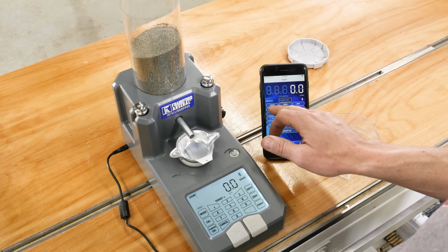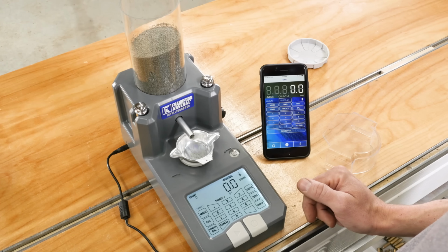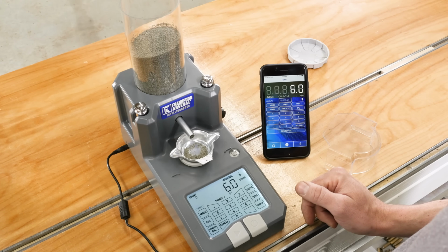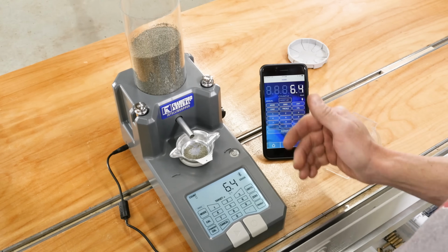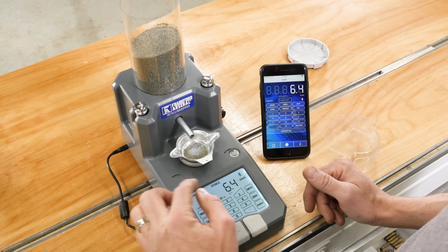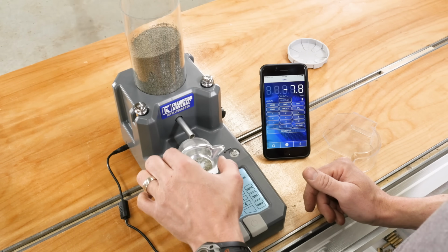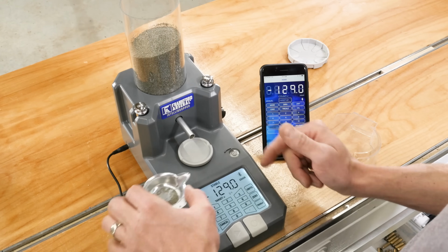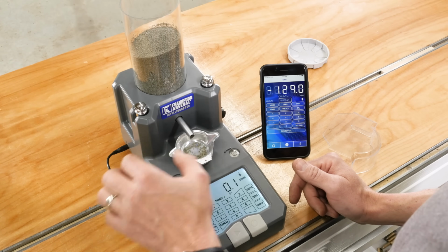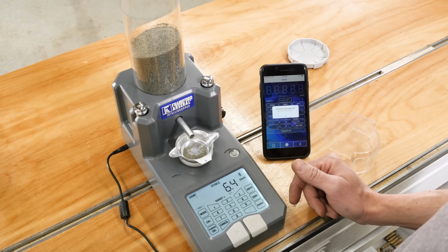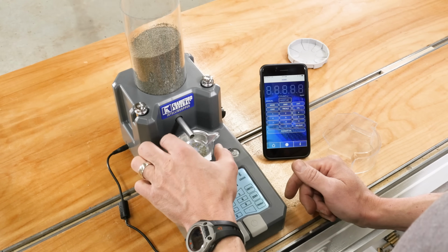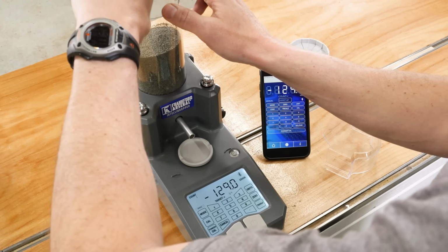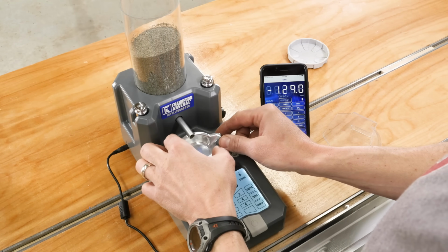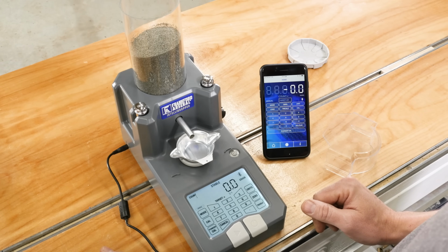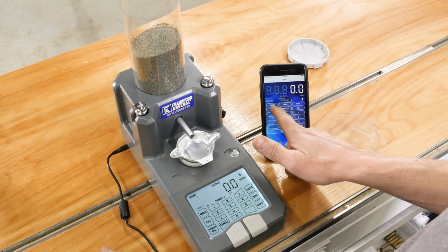Okay. Go ahead and hit the load button here. We can control it either from the unit or from the mobile app. So it looks like it's consistently going to about 0.4 or 0.5 grains under and then trickling up. 6.4 and stable. Super careful. Let it stabilize without the pan on there and then put it back. 6.4 and stable. Okay. 0 and stable. Let's go ahead and hit load.